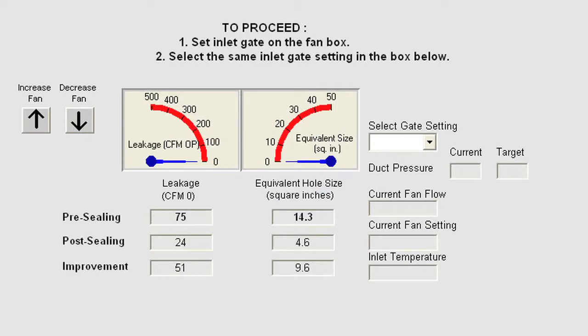So we just wrapped up the post-test after we sealed with Aeroseal, and now we can look at the numbers to see what the leakage was before we sealed, and what the leakage is after we sealed. It's stabilizing, and the test is complete. Now you can see here the post-seal is 24 CFM and the pre-seal is 75 CFM. What that's equivalent to is a 14.3 square inch hole of leakage, and we've sealed that down to a 4.6 square inch hole of leakage.